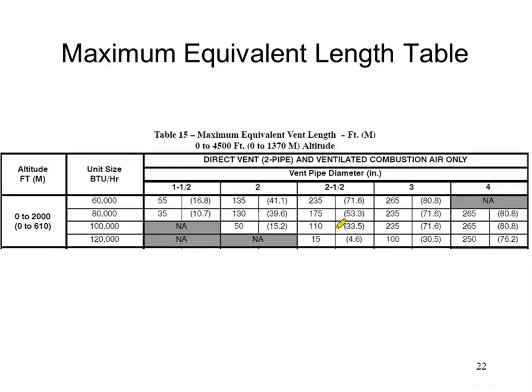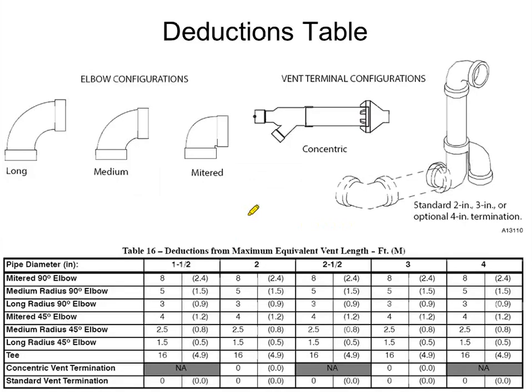All right, so that's how many feet you can run it, right? So let's take our example of 80,000 with 2-inch venting pipe. I can go 130 feet. Let's use that as our example. So I get to 130 equivalent feet. So that's actual linear feet minus any deductions for any of my elbows and things like that. So since I picked 2-inch pipe, I'm in this column over here, right? My venting is already included in that number, so there's no additional penalty for that. They've already assumed we're going to have some kind of venting termination, so I've already got that included.